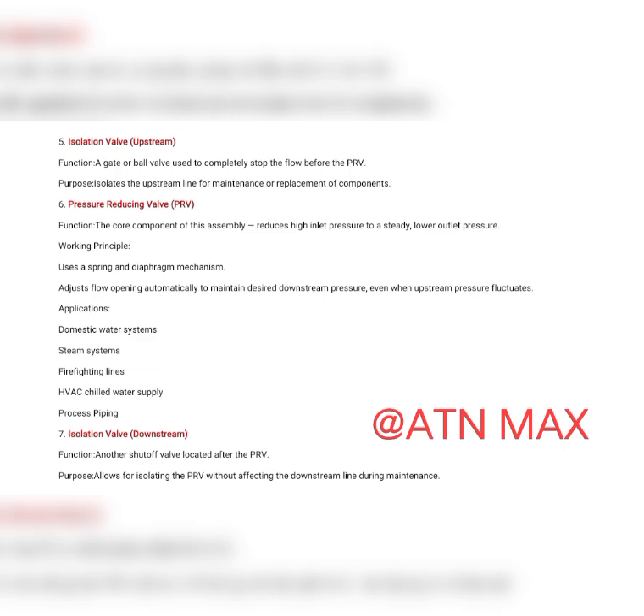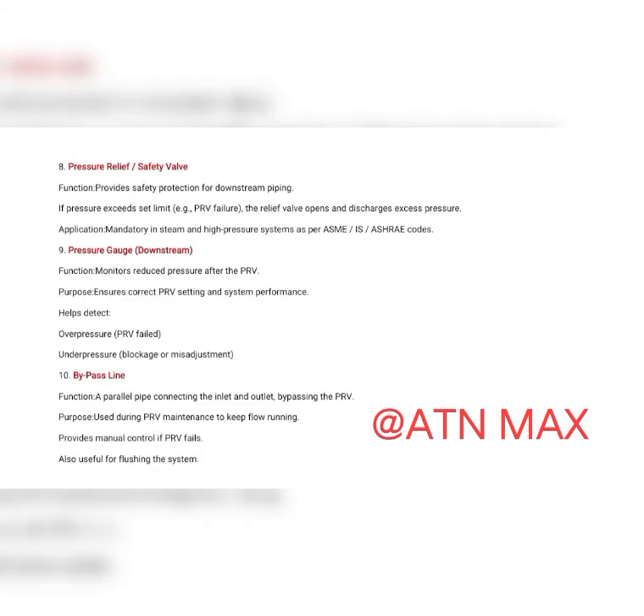7. Isolation valve, downstream. Function: another shutoff valve located after the PRV. Purpose: allows for isolating the PRV without affecting the downstream line during maintenance. 8. Pressure relief/safety valve. Function: provides safety protection for downstream piping. If pressure exceeds set limit, e.g., PRV failure, the relief valve opens and discharges excess pressure.